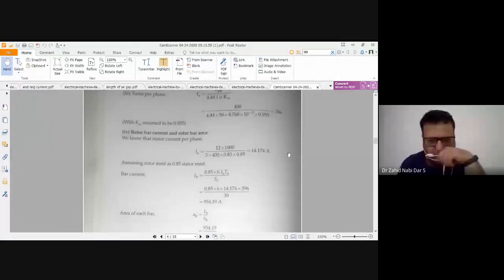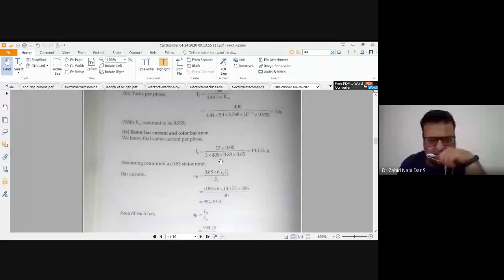This is your power. P would be equal to 3 V stator, power factor of the stator winding, and your efficiency. So you can write I stator would be equal to power divided by 3, V stator, efficiency, power factor. Once you substitute back, you know that your power is 12 kilowatts. So 12 kilowatts divided by 3, this V stator is equal to V rotor. Your efficiency is 83%, 83 divided by 100 would be 0.83. This is 0.85. So you get the value of 14.174 ampere.